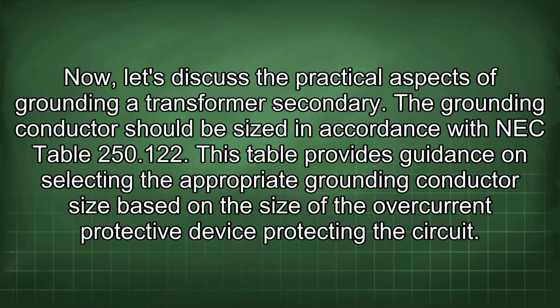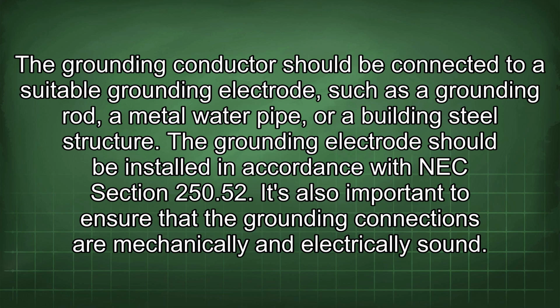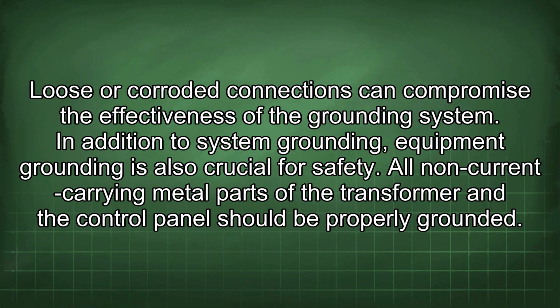Now, let's discuss the practical aspects of grounding a transformer secondary. The grounding conductor should be sized in accordance with NEC Table 250.122. This table provides guidance on selecting the appropriate grounding conductor size based on the size of the overcurrent protective device protecting the circuit. The grounding conductor should be connected to a suitable grounding electrode, such as a grounding rod, a metal water pipe, or building steel structure. The grounding electrode should be installed in accordance with NEC Section 250.52. It's also important to ensure that the grounding connections are mechanically and electrically sound. Loose or corroded connections can compromise the effectiveness of the grounding system.